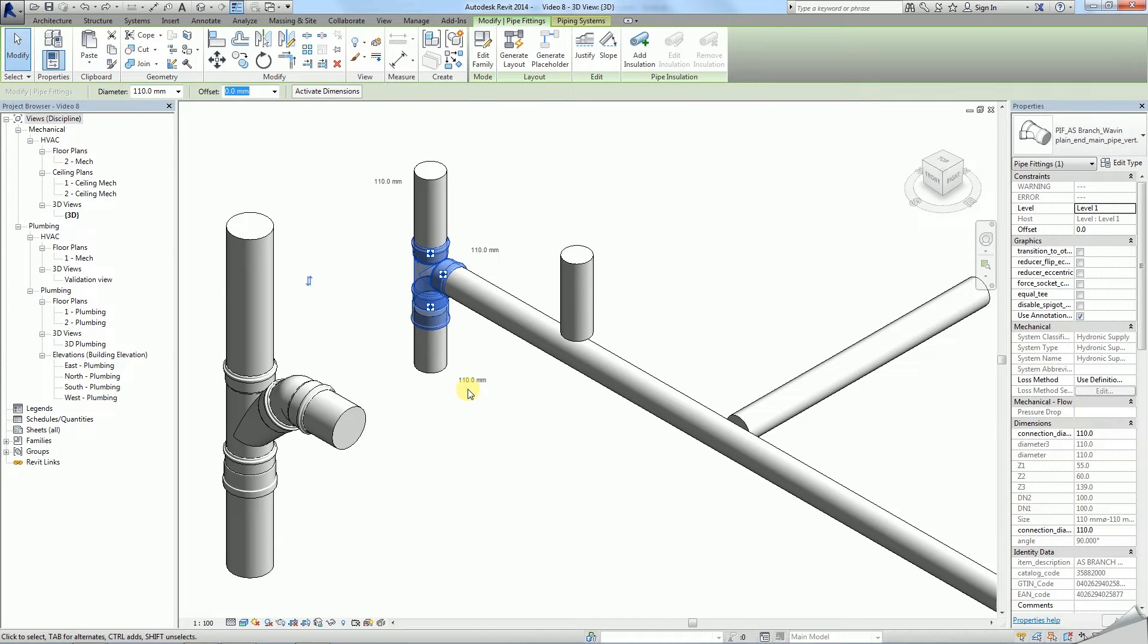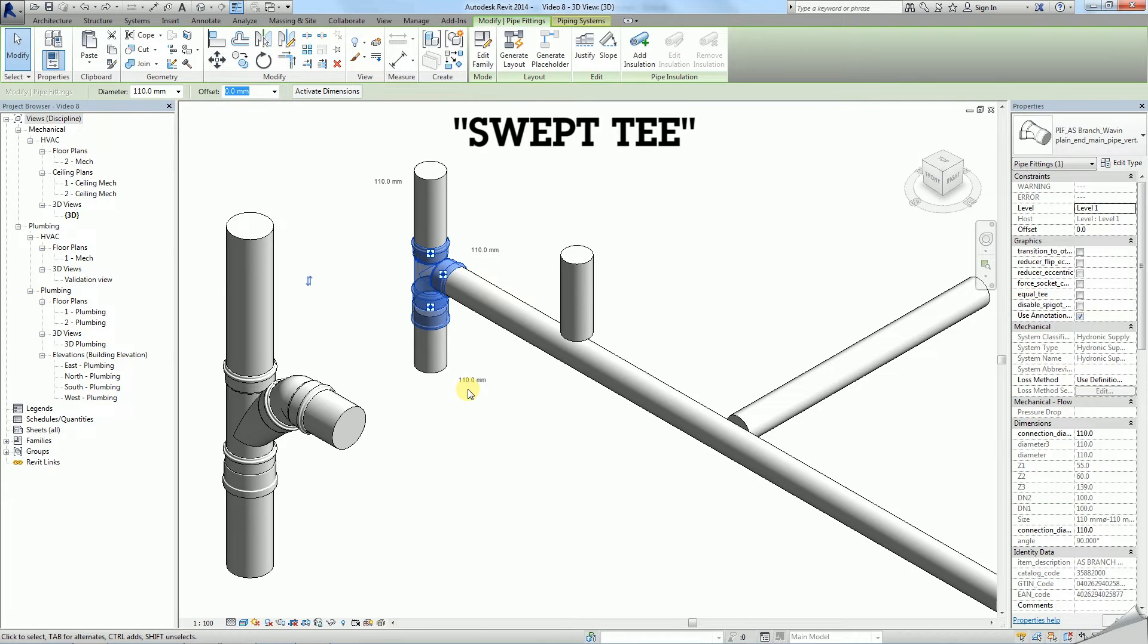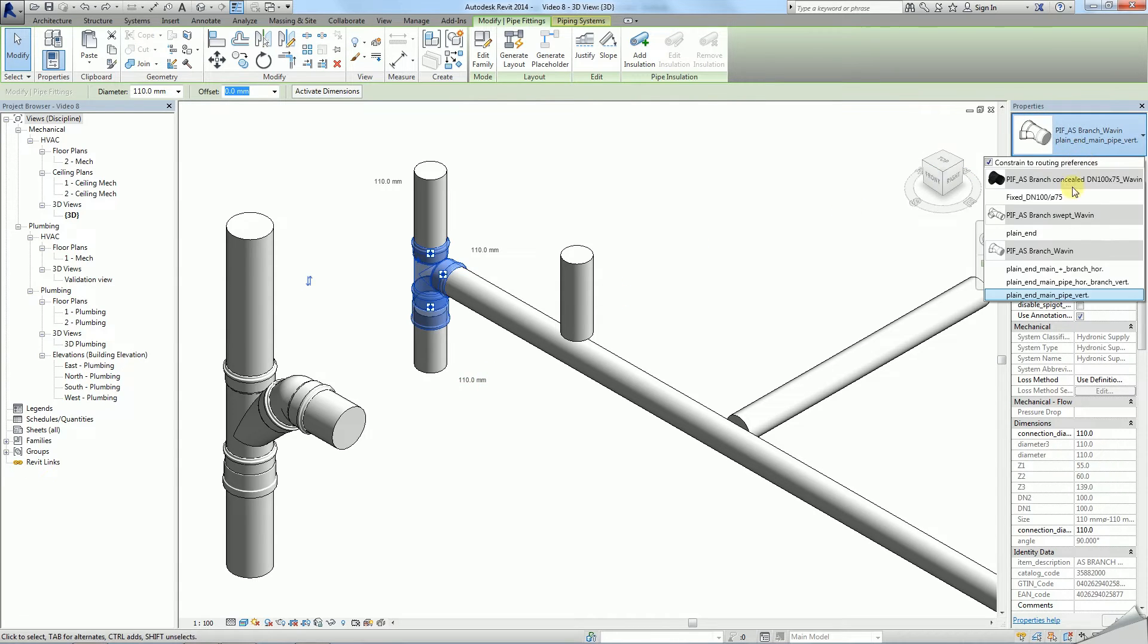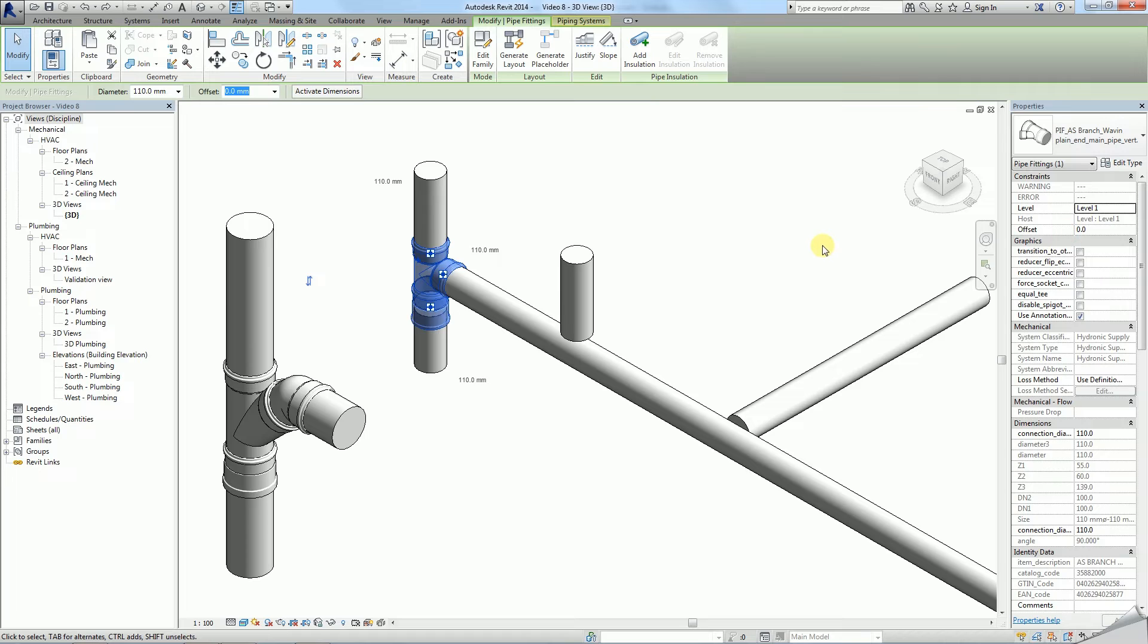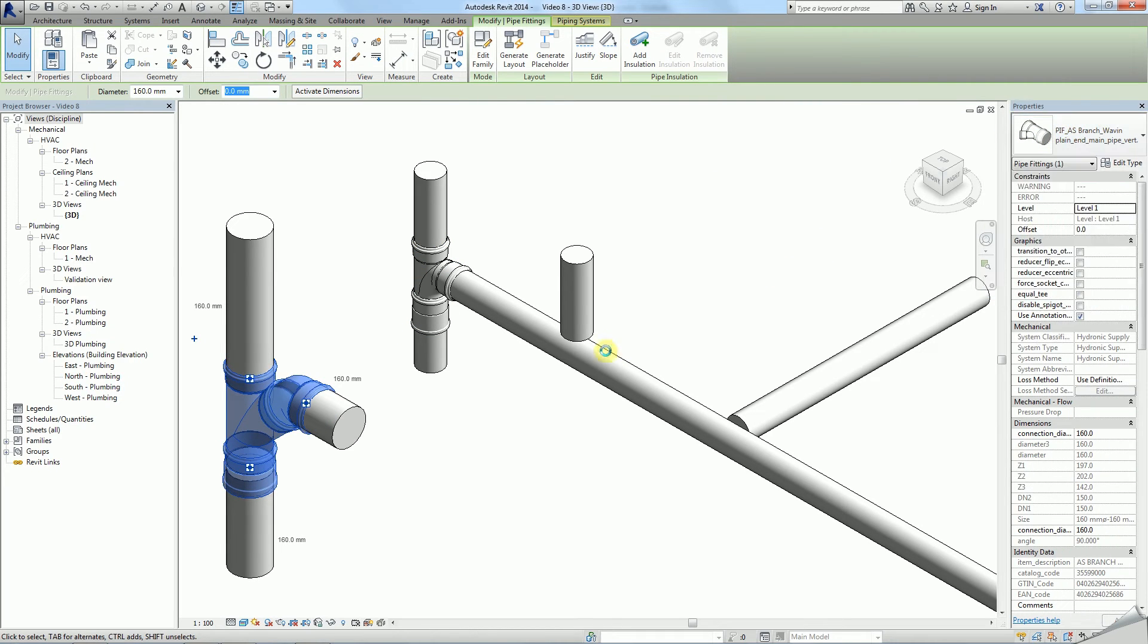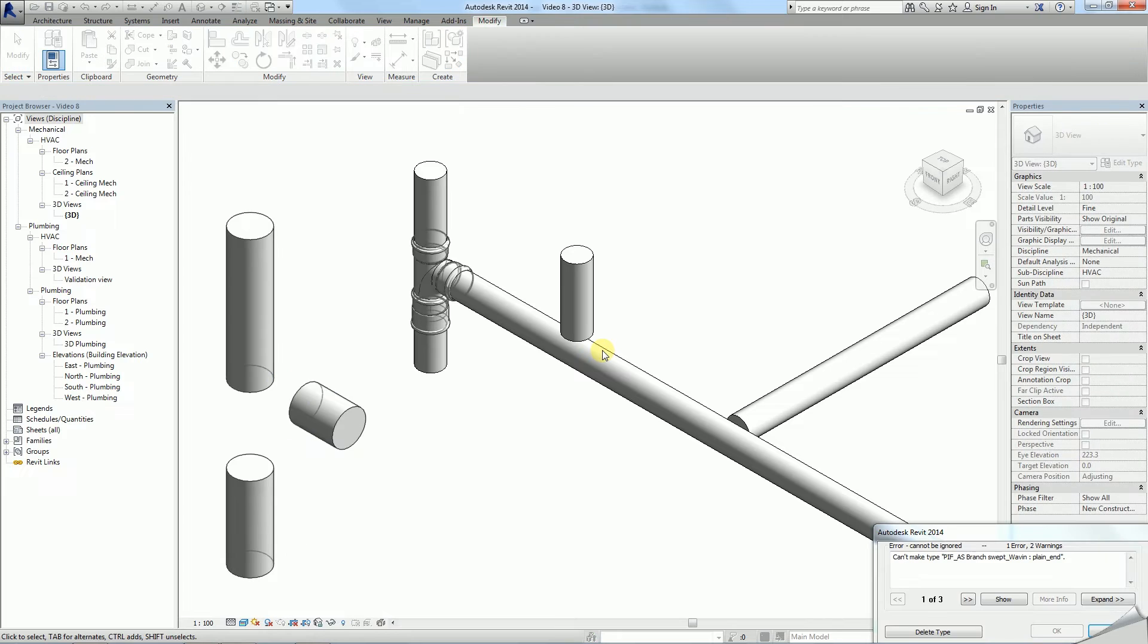An alternative connection to a stack is a swept T. It is available only in a very limited range of diameters. Therefore you can change a 110mm default T into one. But a 160mm T will generate an error because the required fittings are not available.